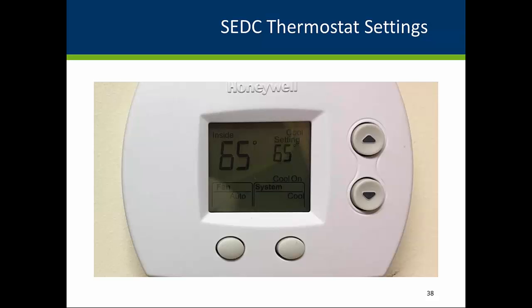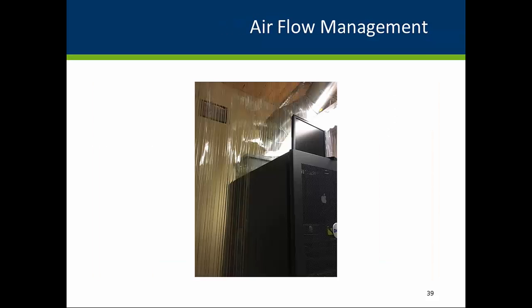At 2 sites with RTUs, we found that during times with no cooling load, the air handler was running continuously. Changing fan settings at the thermostat from on to auto resulted in a 95% reduction in energy use of running the air handler at one site and an almost 60% savings at the other site.